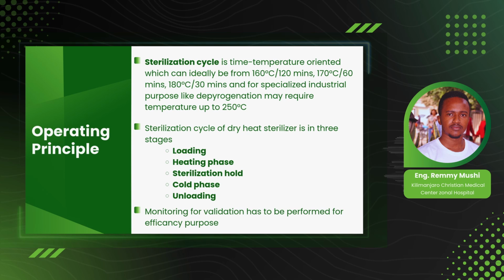So as we have already seen all of the parts of the machine and the types of the machine, now we can move forward to look at the sterilization cycle being used here. The sterilization cycle comes in different modes in this dry heat sterilizer, in which we can sterilize our materials or our load at a temperature of 160 degrees, which will take 120 minutes for sterilization. It can also be 170 degrees or 180 degrees. And as we increase the temperature, the time also decreases, but not in all cases. It will depend on what you need to sterilize.